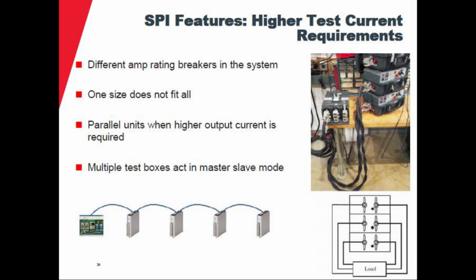And in this case, we have 3 units here, but we are only connecting 2. So you get basically twice the current. So you can get up to 4,000 amps with 2 units, or 4 units can give you up to 8,000 amps. So in some cases where you have bigger breakers, you can use several of the units to test. You can have one in your fleet, and then you can rent one more to be able to test higher breakers. Let's say that could be one way to configure them.